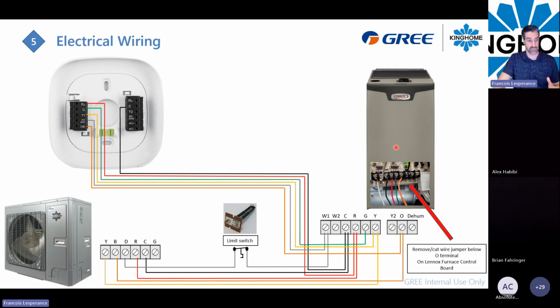So it will short cycle your furnace a little bit, but that will help you to not make the refrigerant hit a high pressure issue. And at the same time, the homeowner will not feel the cold air in the ductwork, because the furnace is brought on for a small amount of time. If the defrost is longer, 7, 8, 9 minutes, the longest it can take is 10, well, if the limit switch closes again, the furnace will be brought back on, and we will do the same pattern again. So by adding this kind of limit switch, it's just some tips and tricks I give you this morning. This is some sort of installation I've done in the past when I was on the field.